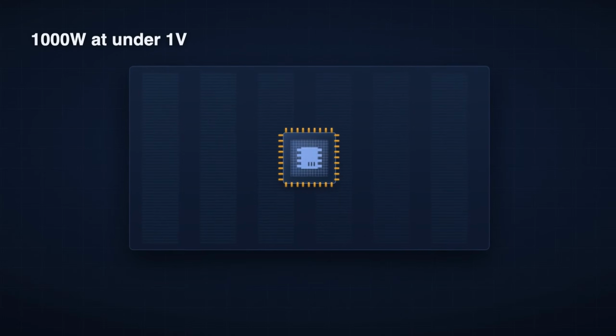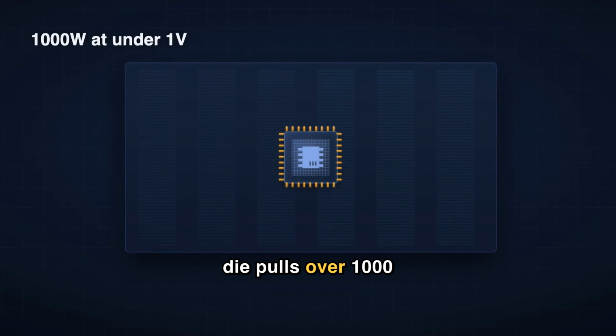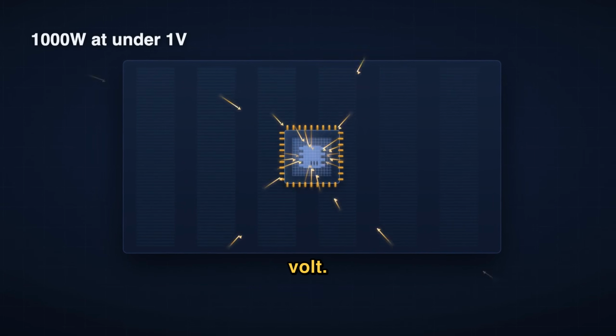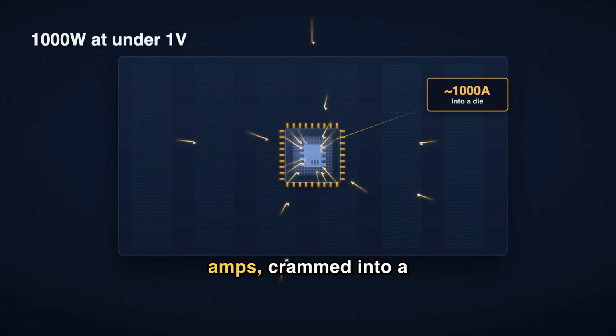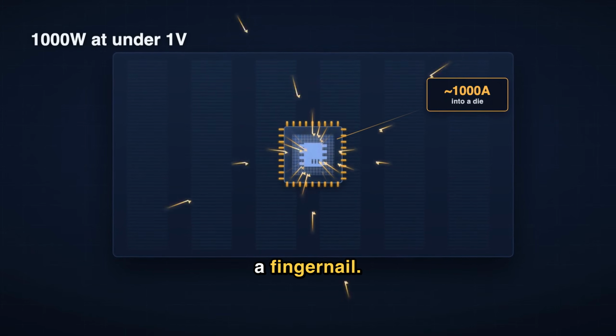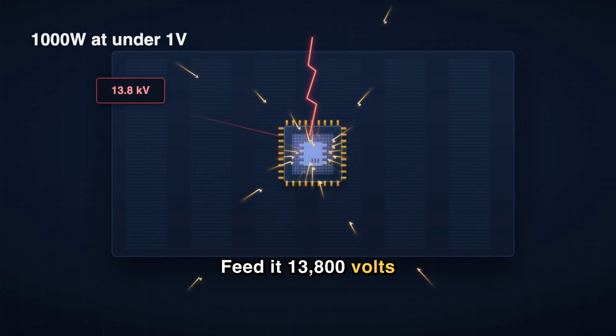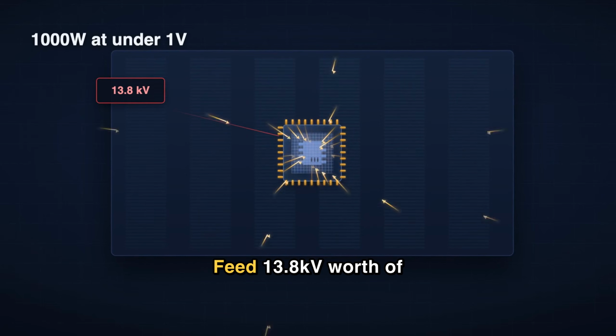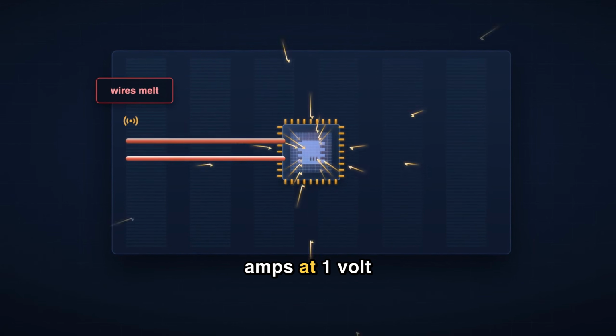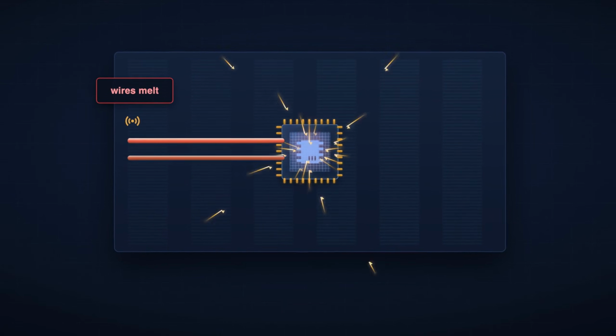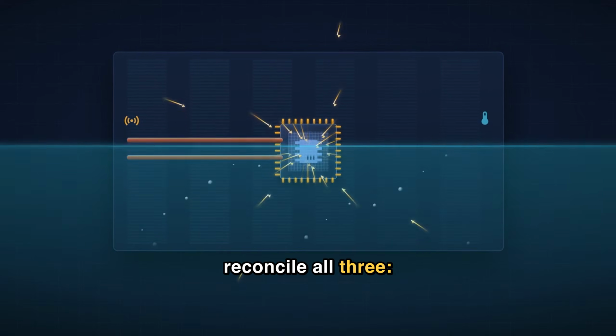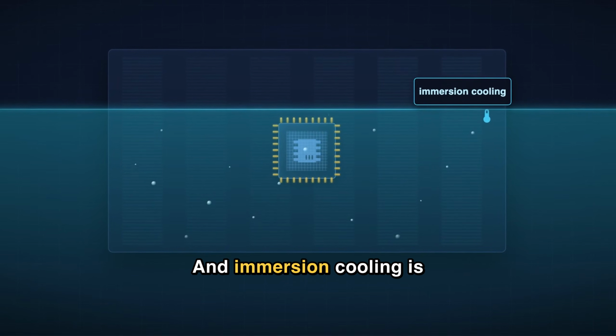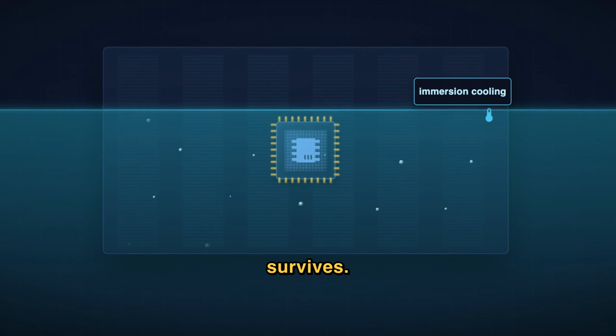Here's the trap. A modern AI GPU die pulls over 1,000 watts at under 1 volt. That's hundreds, nearly 1,000 amps, crammed into a chip the size of a fingernail. Feed it 13,800 volts and the die vaporizes. Feed 13.8 kilovolts worth of amps at 1 volt and the wires melt. The network exists to reconcile all three: voltage, current, and heat. And immersion cooling is the only reason this survives.